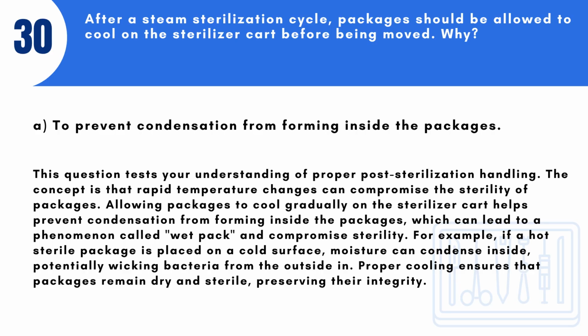Answer: A. To prevent condensation from forming inside the packages. This question tests your understanding of proper post-sterilization handling. The concept is that rapid temperature changes can compromise the sterility of packages. Allowing packages to cool gradually on the sterilizer cart helps prevent condensation from forming inside the packages, which can lead to a phenomenon called wet pack and compromise sterility. For example, if a hot sterile package is placed on a cold surface, moisture can condense inside, potentially wicking bacteria from the outside in. Proper cooling ensures that packages remain dry and sterile, preserving their integrity.